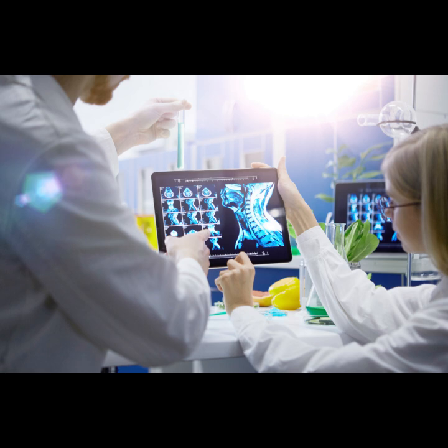Exactly. It applies a weak gradient, gets a line of data, then a slightly stronger one gets another line, then stronger still. It needs to do this for every single line of data it wants to collect in that y dimension, say 256 times for a typical image. And each repetition takes time. The TR, the repetition time. Bingo. And that is the primary reason why standard high-resolution MRI scans take minutes, not seconds. Filling up all those phase encoding steps just takes time.